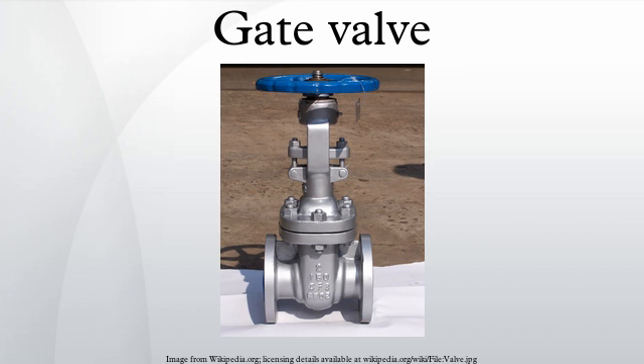Bonnets provide leak-proof closure for the valve body. Gate valves may have a screw-in, union, or bolted bonnet. Screw-in bonnet is the simplest, offering a durable, pressure-tight seal. Union bonnet is suitable for applications requiring frequent inspection and cleaning, and also gives the body added strength. Bolted bonnet is used for larger valves and higher pressure applications.